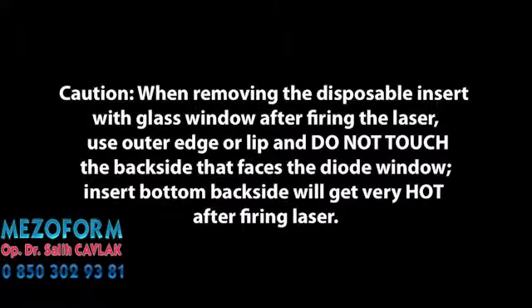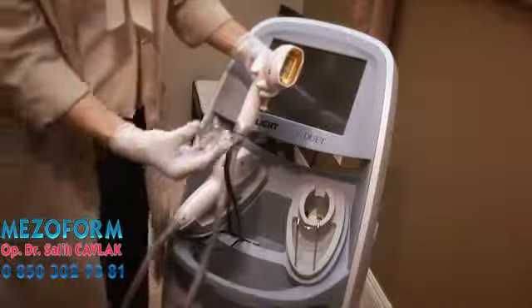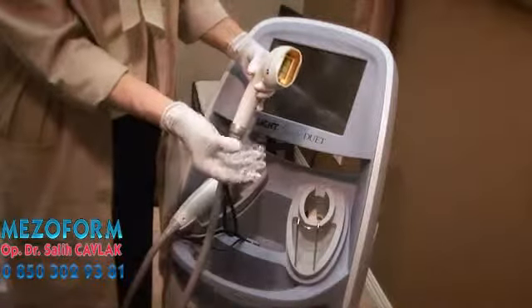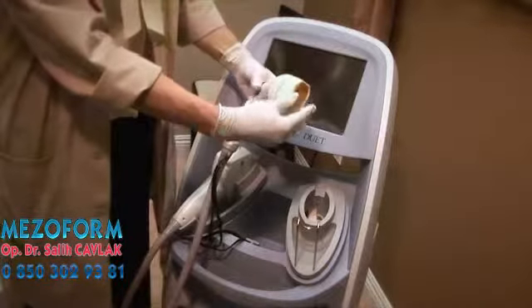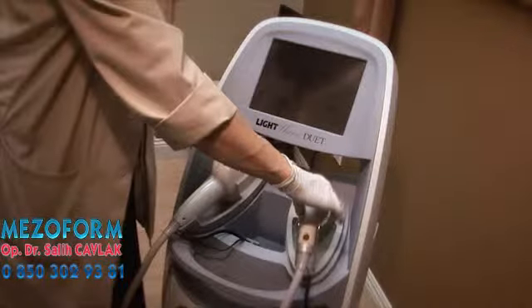Caution: when removing the disposable insert with glass window after firing the laser, use the outer edge or lip and do not touch the backside that faces the diode window. The insert bottom backside will get very hot after firing laser. Following each treatment, the disposable insert must be removed, and a new and clean insert should be inserted into the handpiece and placed in the system holster.